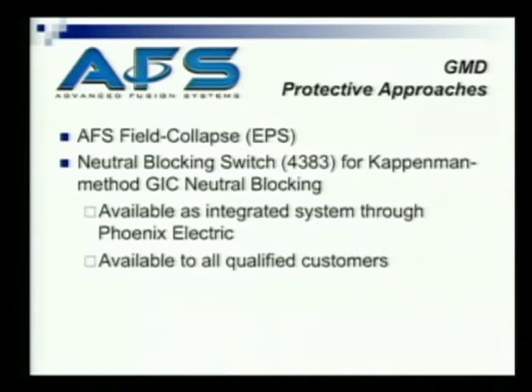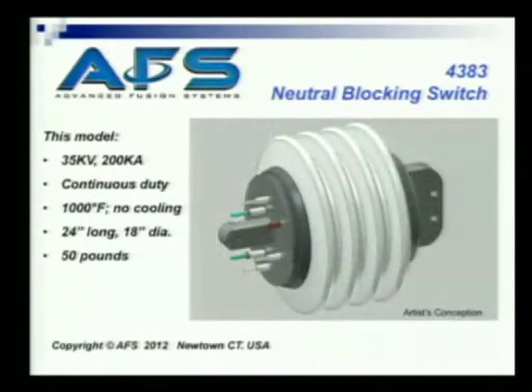AFS has some protective approaches for GMD. The field collapse EPS system takes care of E1 and E3. We also have a neutral blocking device for the Kappenman method of GIC neutral blocking. That's available as an integrated system through Phoenix Electric, and also available as a switch itself to all qualified customers. It looks like this at 35 kV and 200 kA — 24 inches long, 18 inches in diameter.